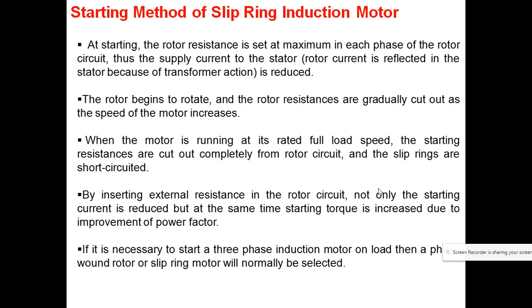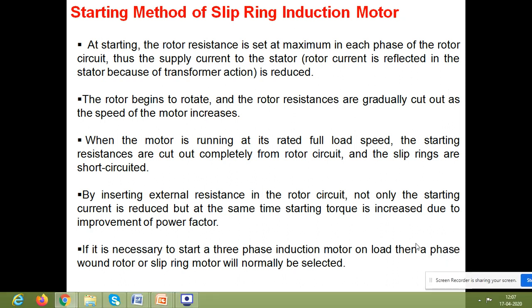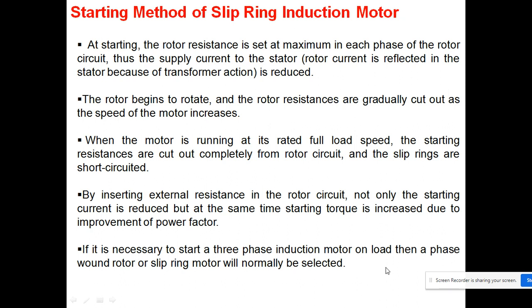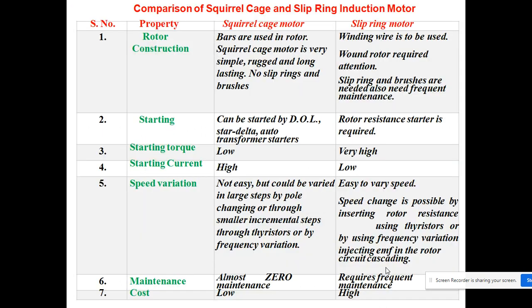By inserting external resistance in the rotor circuit, not only is the starting current reduced, but at the same time the starting torque is increased due to improvement in the power factor. And this type of motor we use when it is necessary to start the three-phase induction motor on load. In that condition, we prefer to use the phase wound motor. So this is all about the starting method of the slip ring induction motor.